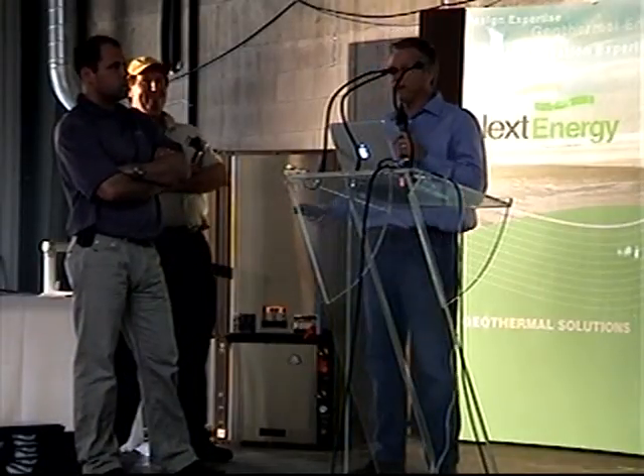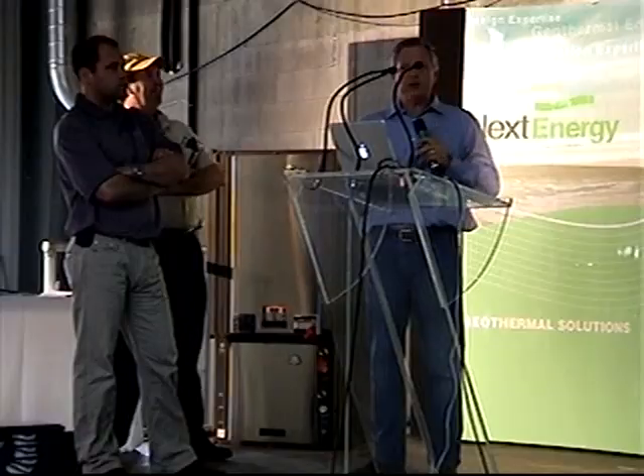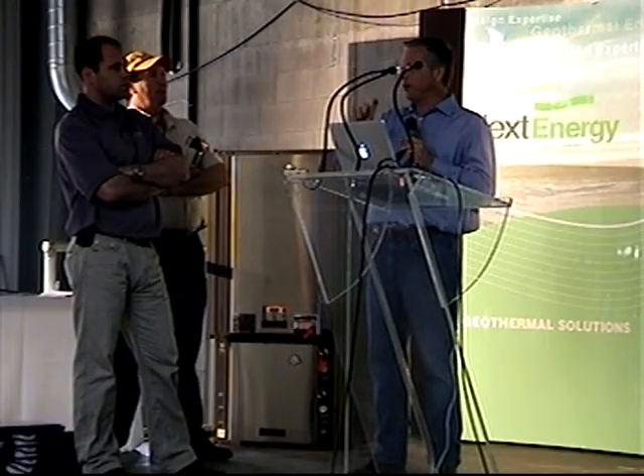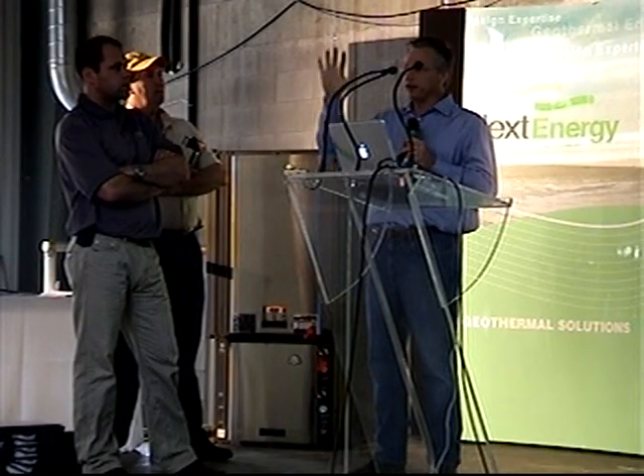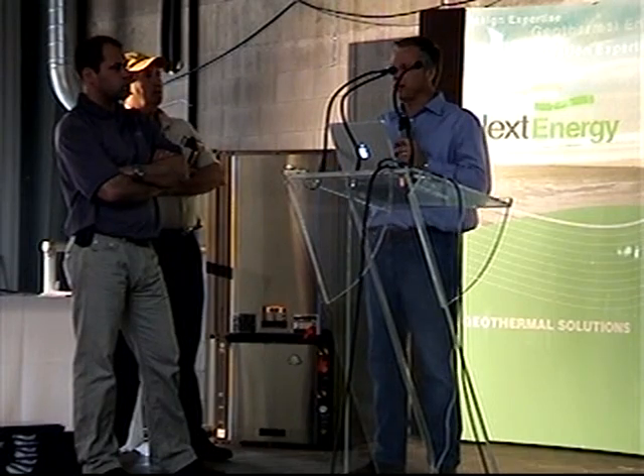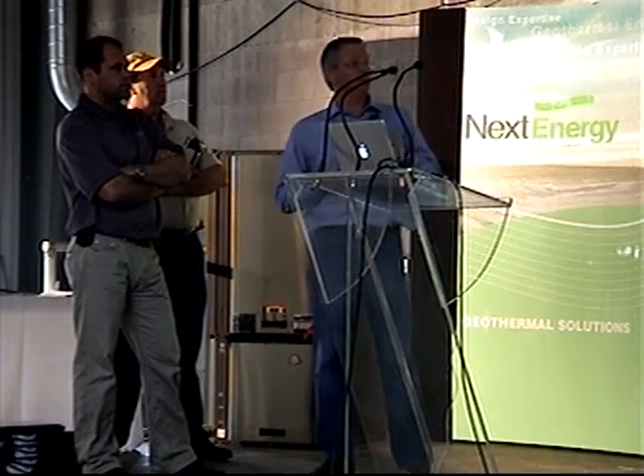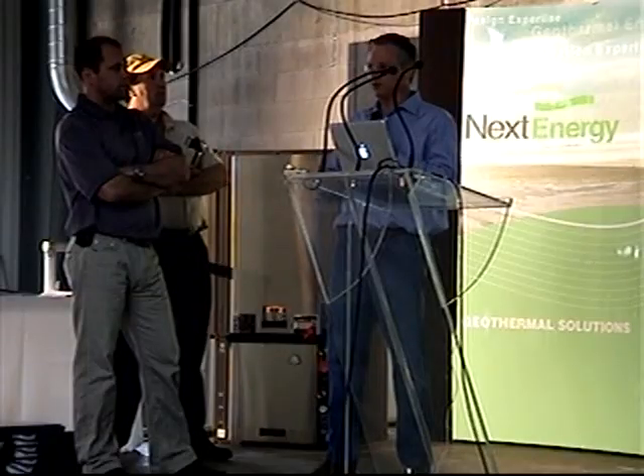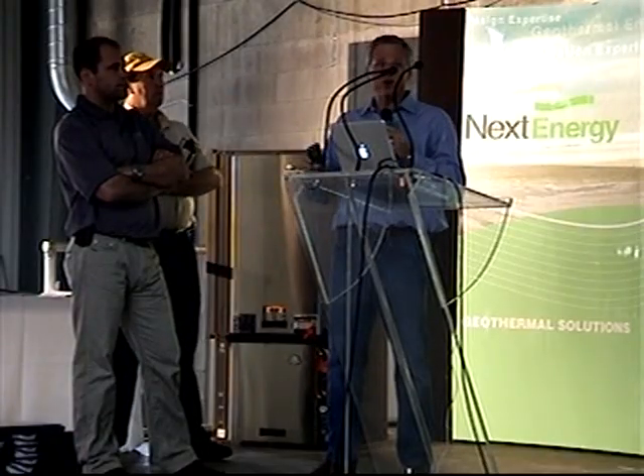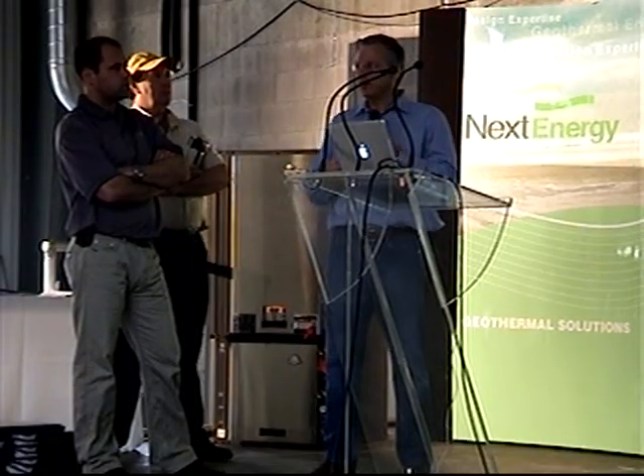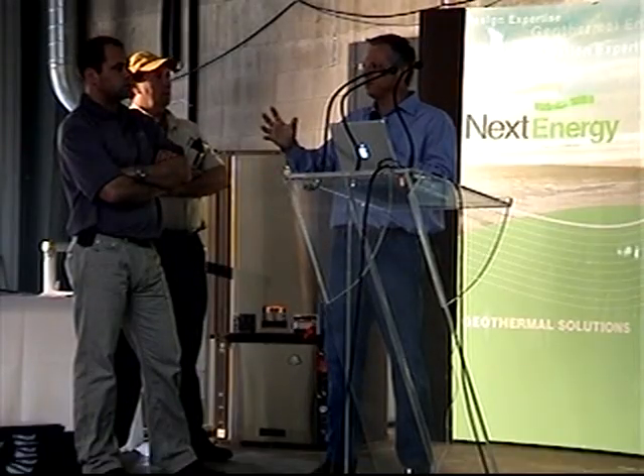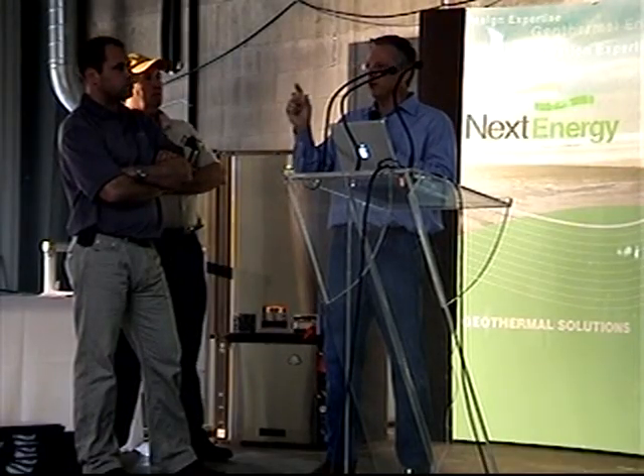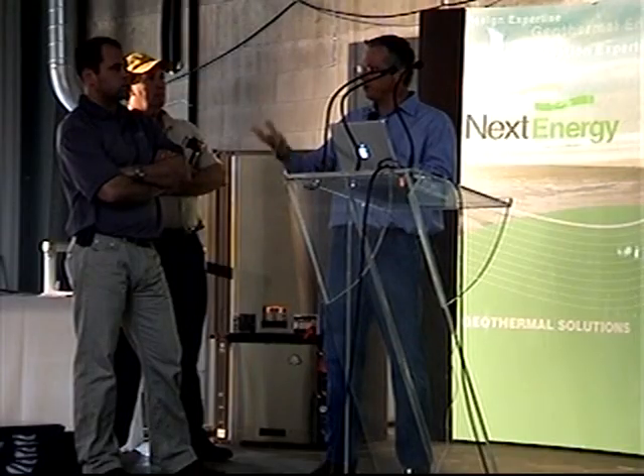And what's going on here? What we do is, you don't want nuisance trip outs. If you put a low pressure switch in the low line and you have a drawdown at the beginning of the cycle, you can get a nuisance trip. So we just found that when you have systems that are splits, whatever, where you don't know what's going on in terms of that, if you're trying to just do loss of charge, all we do is we look at it when the unit is off, not when it's on.